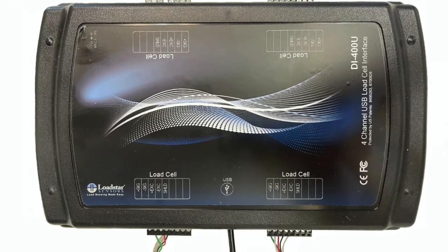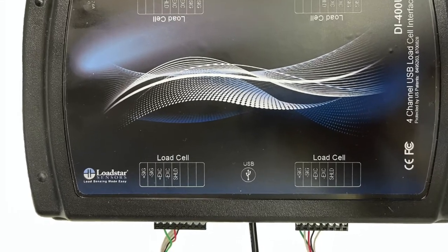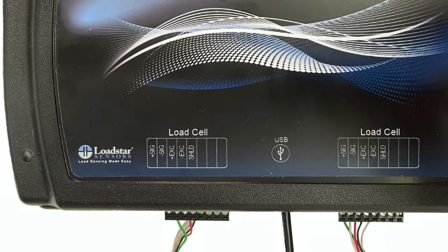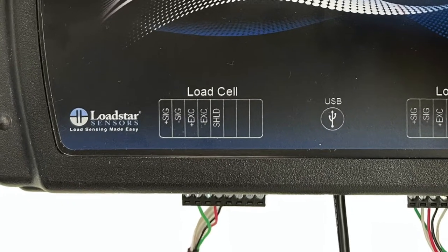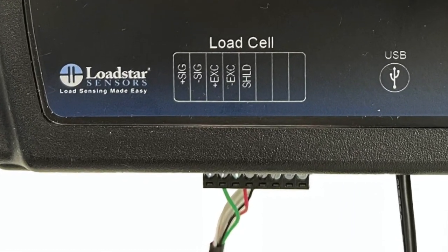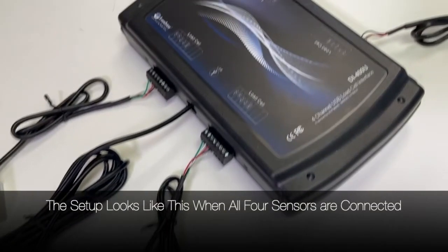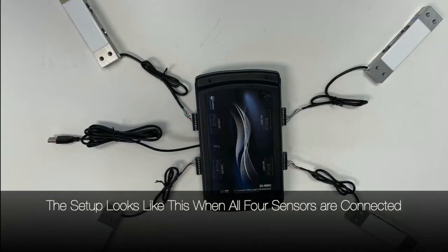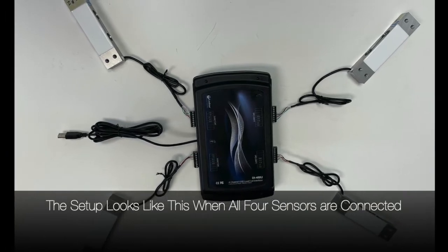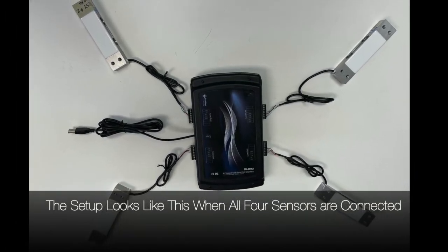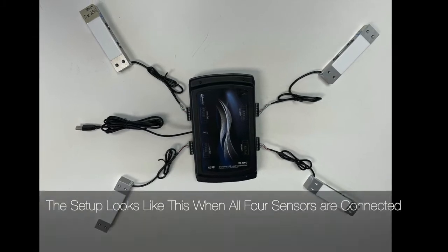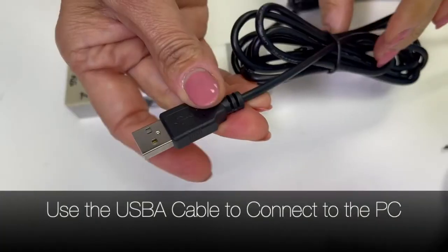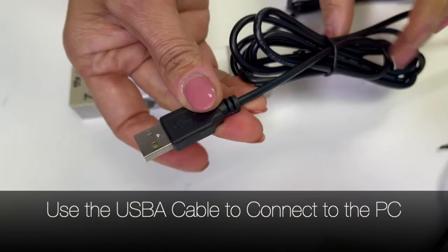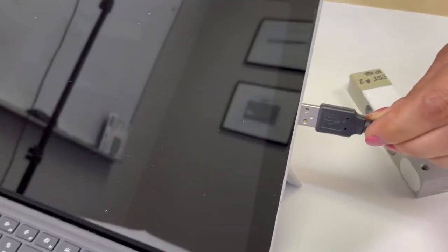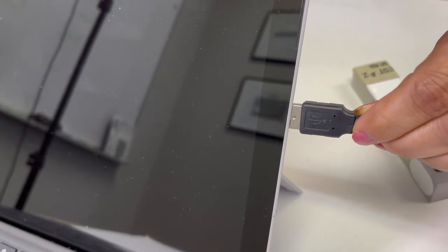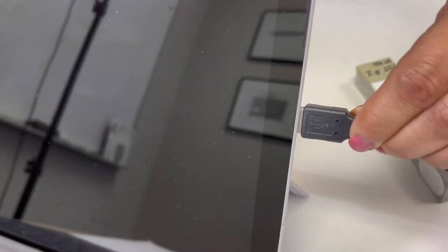Start by connecting the load cell to the terminal block and then inserting the terminal block into DI-400U. You can refer to the wiring guide on the label. Connect all 4 load cells into the 4 ports provided on DI-400U. You can connect any 4-wire resistive load cell to the DI-400U. Use the USB-A connector to connect the DI-400U to your PC or tablet. The load cells and DI-400U are powered by the USB connected to the PC.